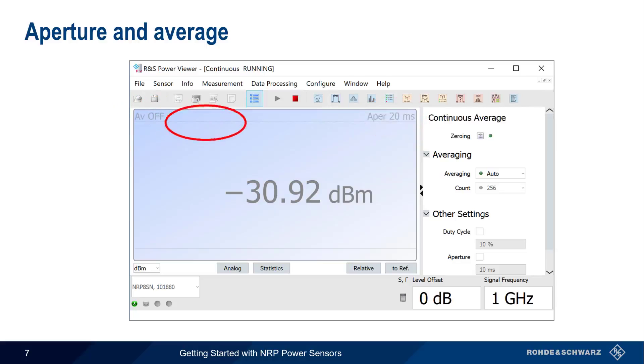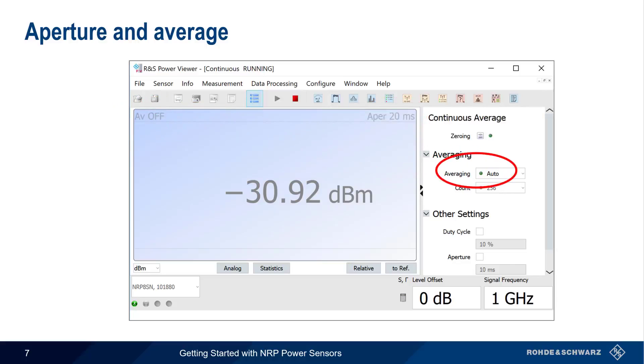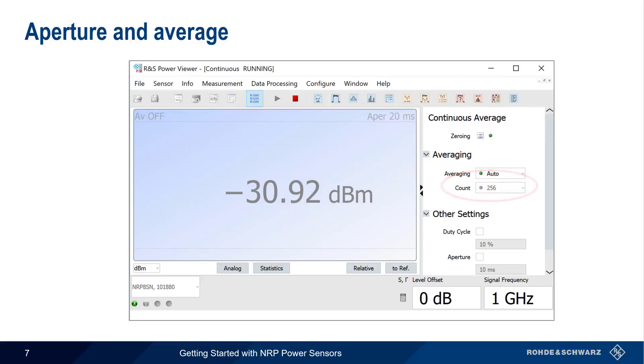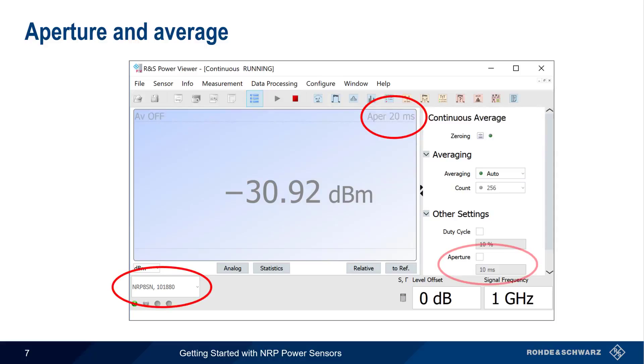Power Viewer uses 'Average Off' to indicate that the average count is being automatically set by the application — in this case, the count is 256. The 20-millisecond aperture value was configured automatically based on the connected sensor type. You can, however, easily override this value if necessary.